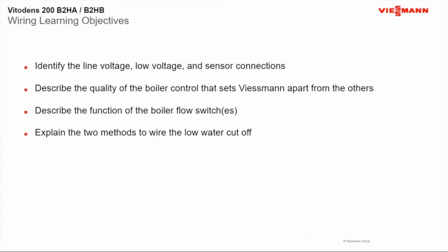So once you learn our system of wiring, and our sensors are auto-recognized, so as soon as you plug in a domestic sensor or anything like that, it auto-recognizes it. So you'll see as we go along as well as that. We'll talk about your functions of your boiler flow switches and sensors, because on the smaller boilers, they have flow switches. On the much larger boilers, the larger boilers have flow sensors.